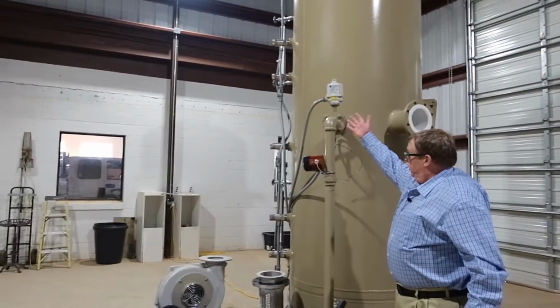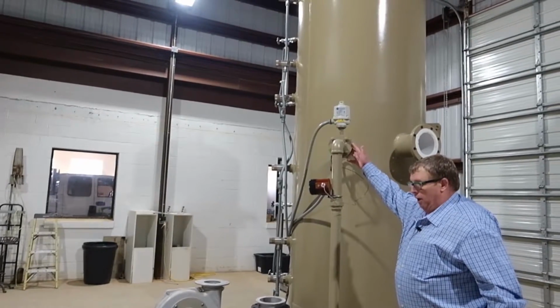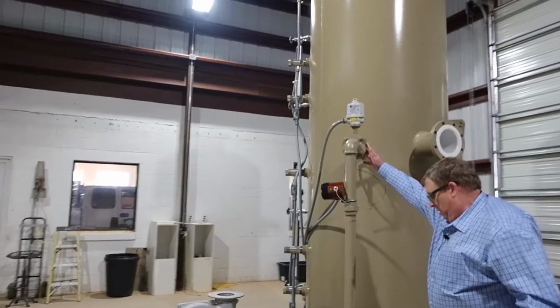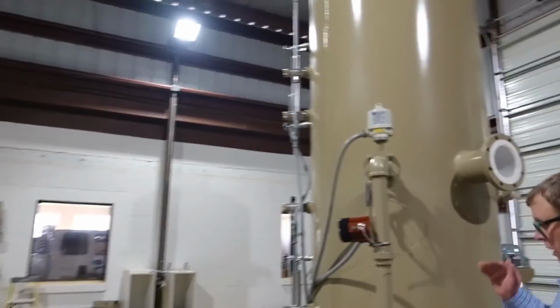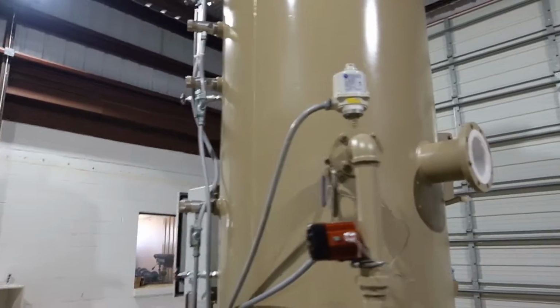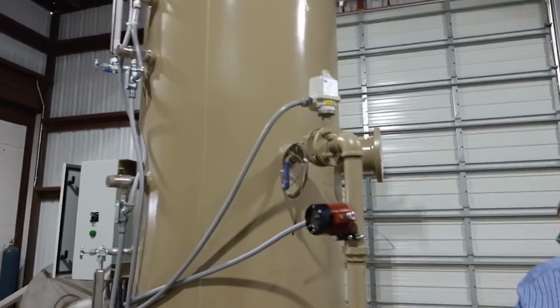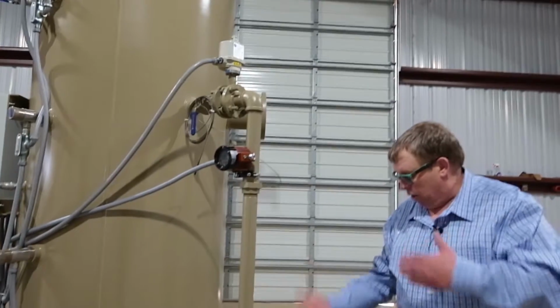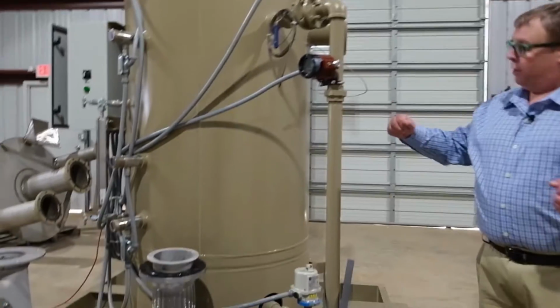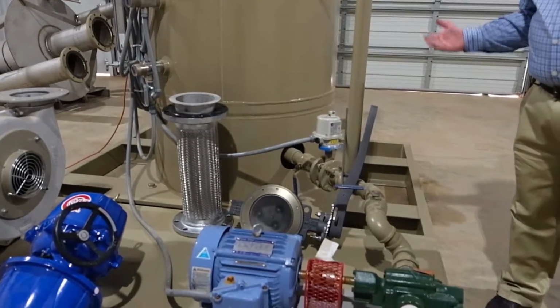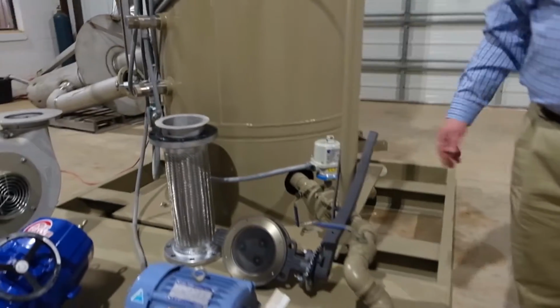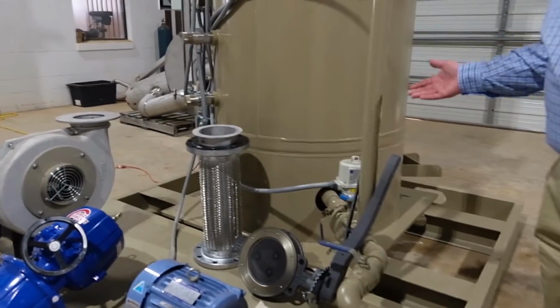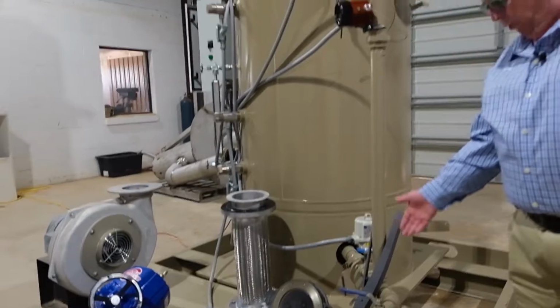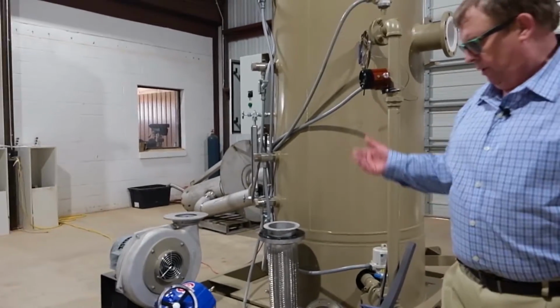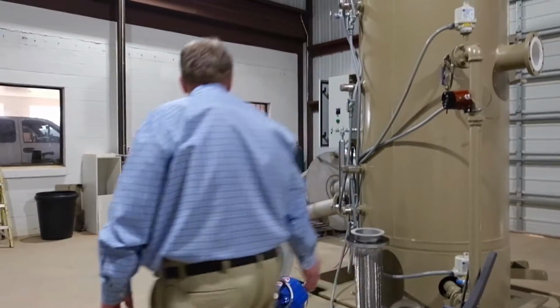If you'll notice, we use actuators and butterfly valves on the liquid process so that we can prevent any kind of backlash or high pressure going against your low pressure. We also have installed some manual ball valves here just for the use of maintenance. When you're keeping up with your flare or you're doing your PMs, you want to have a way of evacuating these liquids without having to use the pump.